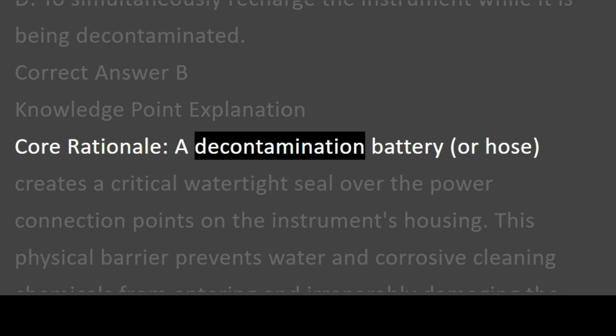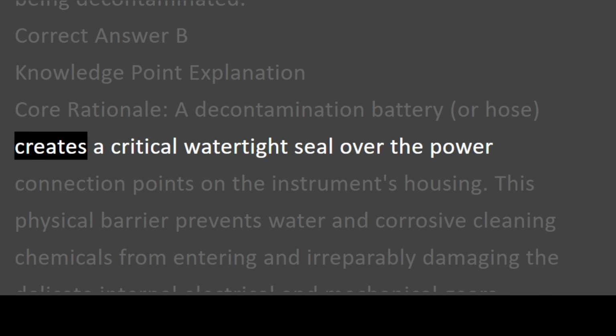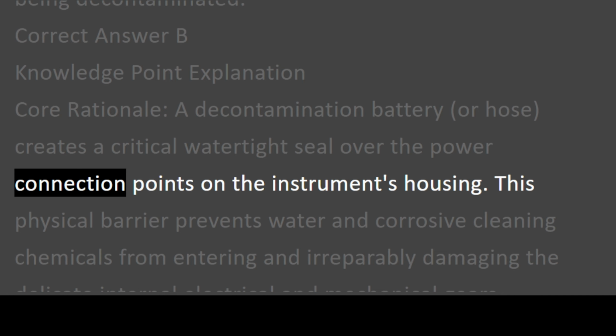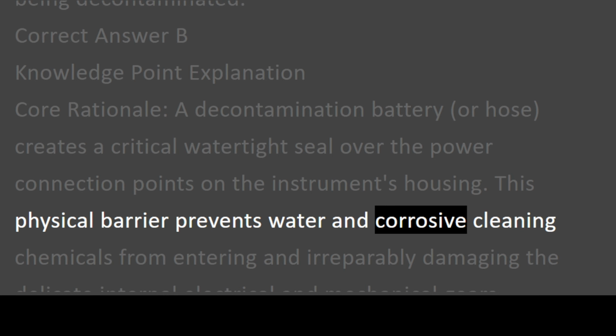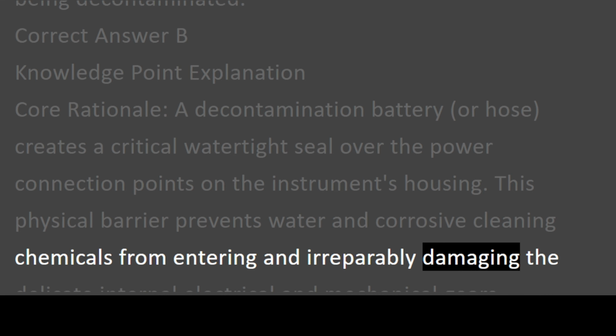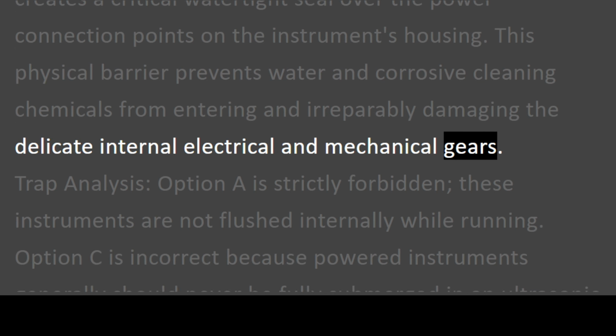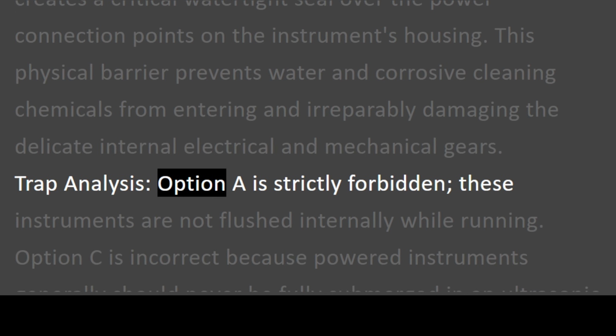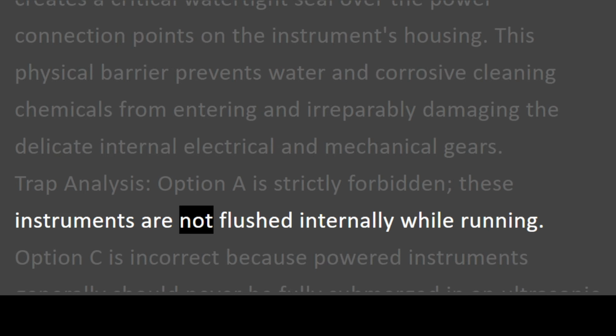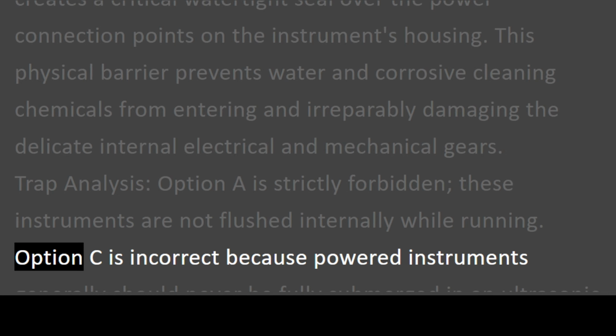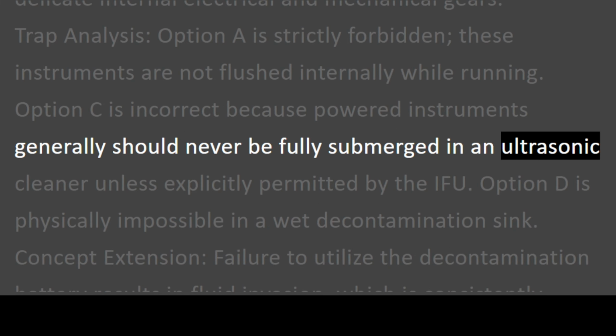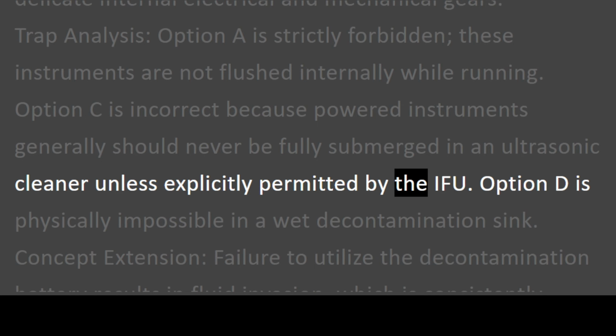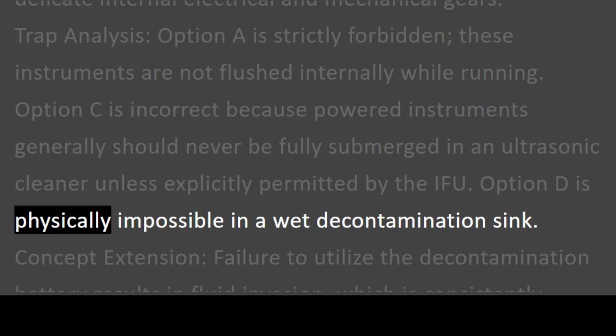Core rationale. A decontamination battery, or hose, creates a critical watertight seal over the power connection points on the instrument's housing. This physical barrier prevents water and corrosive cleaning chemicals from entering and irreparably damaging the delicate internal electrical and mechanical gears. Trap analysis. Option A is strictly forbidden. These instruments are not flushed internally while running. Option C is incorrect because powered instruments generally should never be fully submerged in an ultrasonic cleaner unless explicitly permitted by the IFU. Option D is physically impossible in a wet decontamination sink.